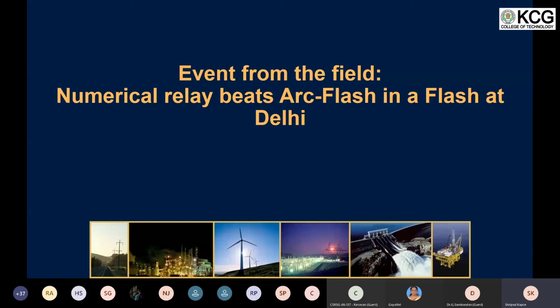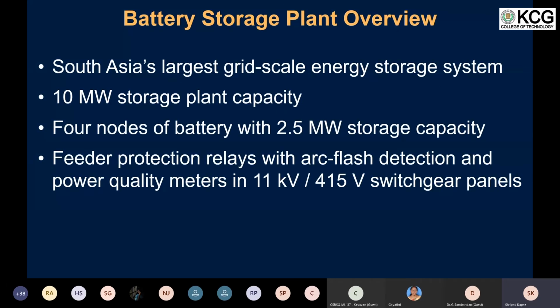Now I'm going to discuss an actual event, and we are going to see how what we discussed in the earlier slide helps us understand how the system operates in an actual fault. We had installed one such system in a grid-tied battery storage plant. This particular battery storage plant is in Delhi, in the Tata Power Delhi distribution network. They have installed this grid-tied battery storage plant, one of South Asia's largest, with a capacity of about 10 megawatt of storage, and each node having up to 2.5 megawatt of storage capacity.